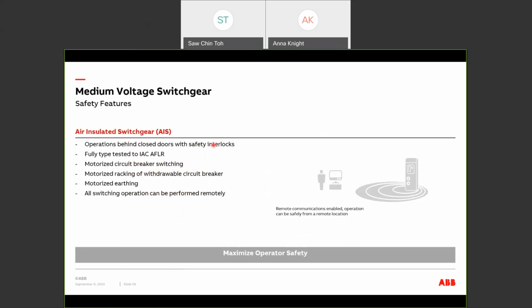ABB panels are already designed and built with safety in mind. Operation of the switchgear is carried out behind a closed door with all the safety interlocks included. Access to the live parts is only permitted when the panels are properly isolated and earthed. All the panels are internal arc AFLR tested, and to further improve safety, we also have options for the racking of the circuit breakers to be done remotely, and the motorized earthing can be done remotely as well. So the main point is to remove the operators from operating the live switchboard in front of the cubicles, and we can do it very, very safely from a remote location.